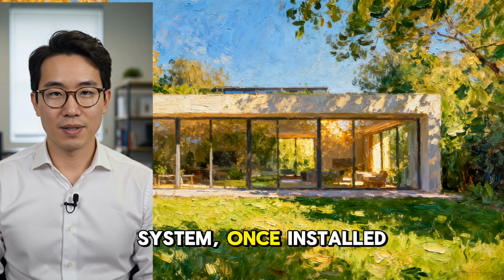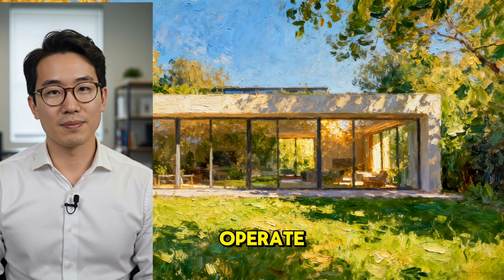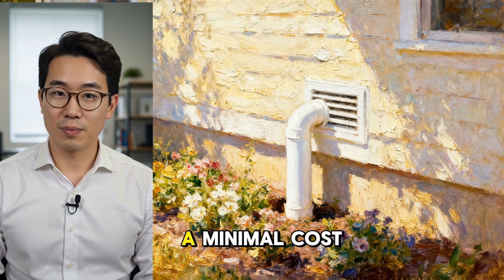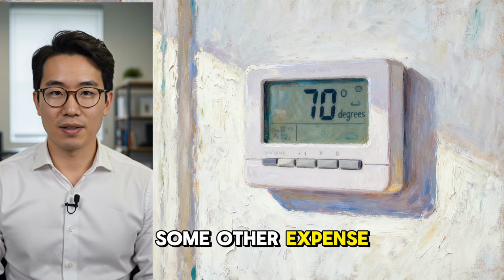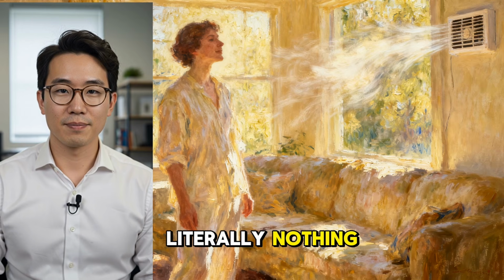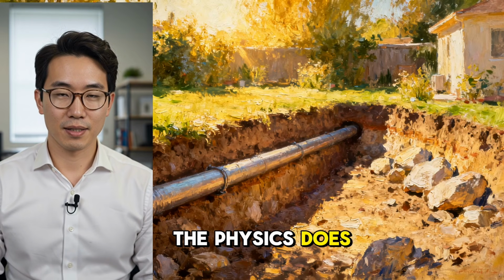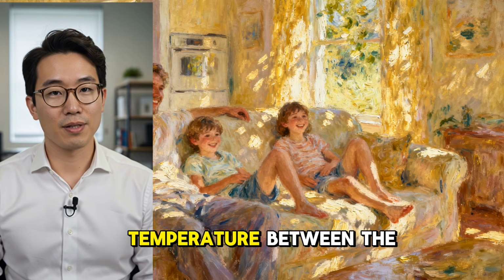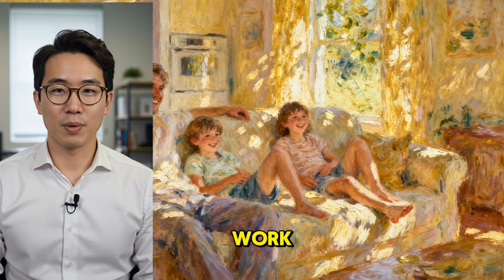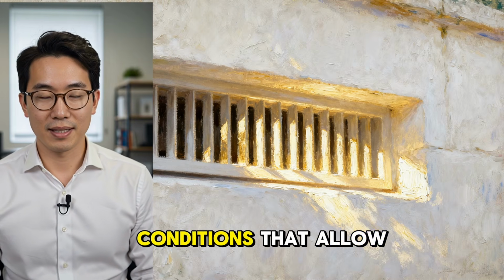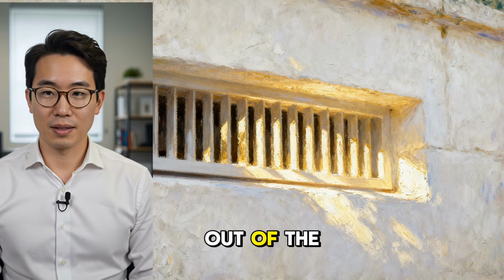An earth tube system, once installed, costs nothing to operate. Nothing. Not reduced to a minimal cost. Not offset by some other expense. Literally nothing. The ground does the work. The physics does the work. The differential in temperature between the surface air and the buried earth does the work. The system simply creates the conditions that allow it to happen and then gets out of the way.